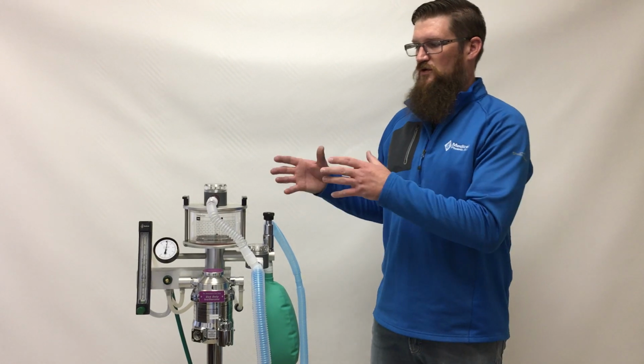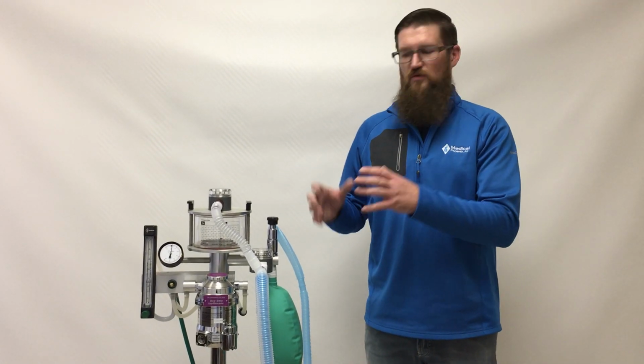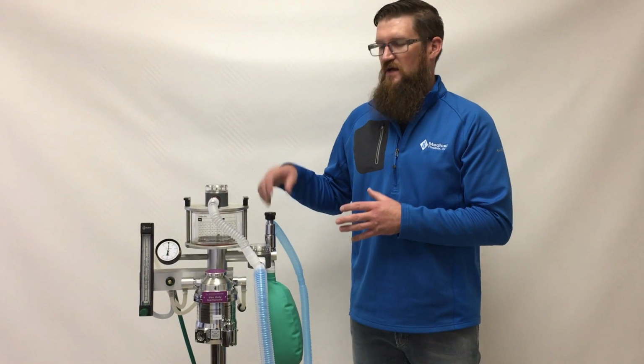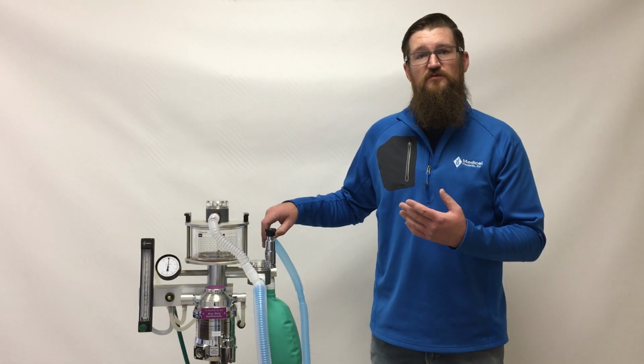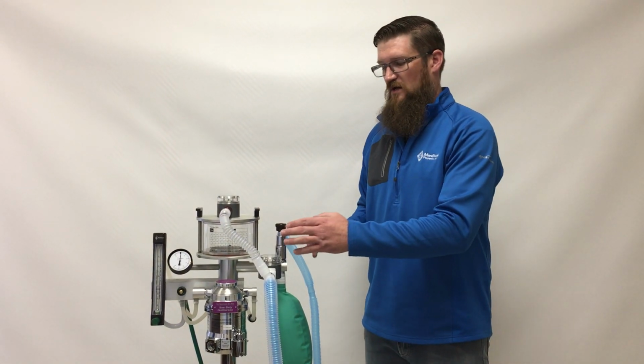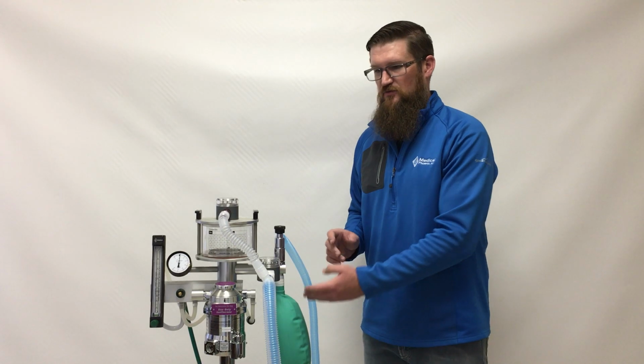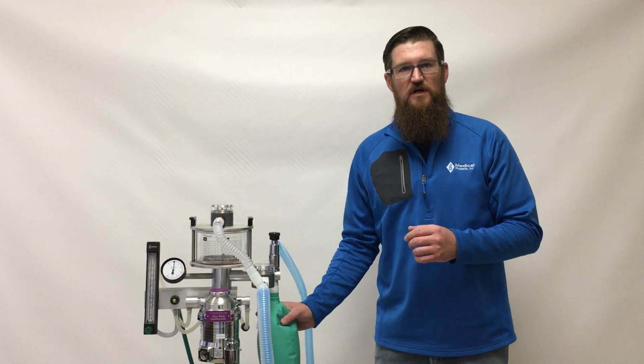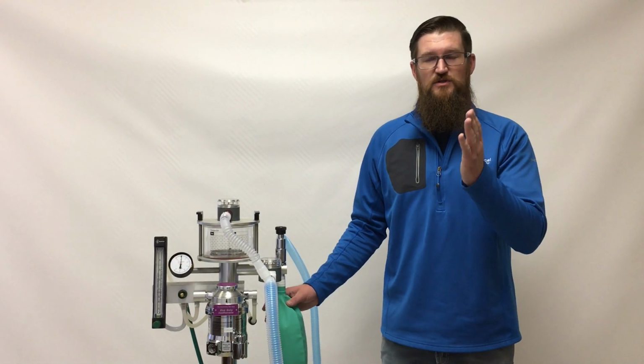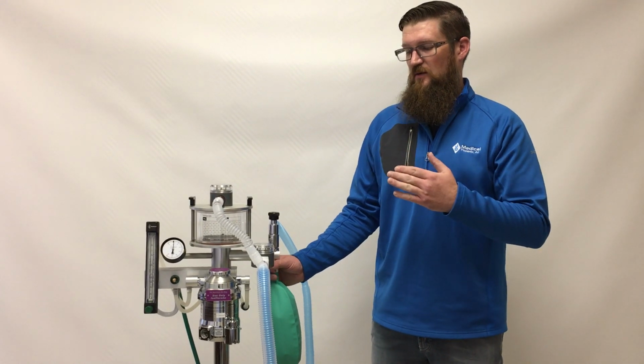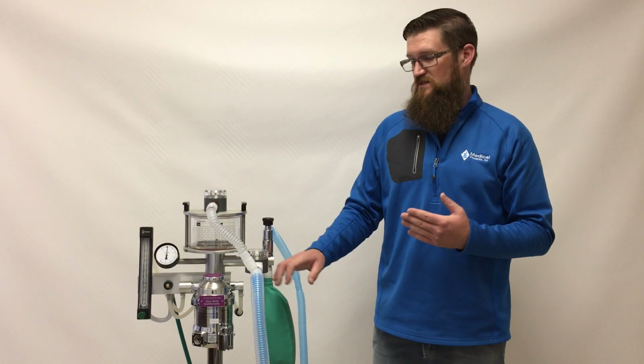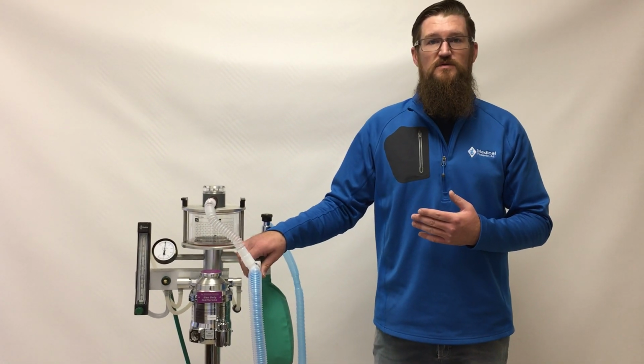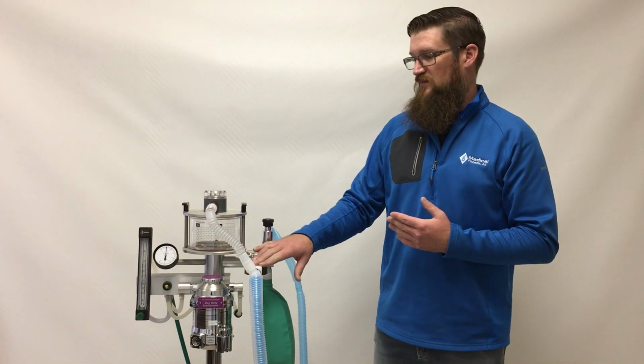In prolonged use for resuscitation or for bagging the patient, you may have to supplement with a little extra oxygen flow, as over time more gas will be vented out through the valve in small increments every time that you squeeze the bag and it goes over that 20 centimeter threshold. But under normal bagging circumstances, it's not a problem to resuscitate using the valve and keeping that in place.